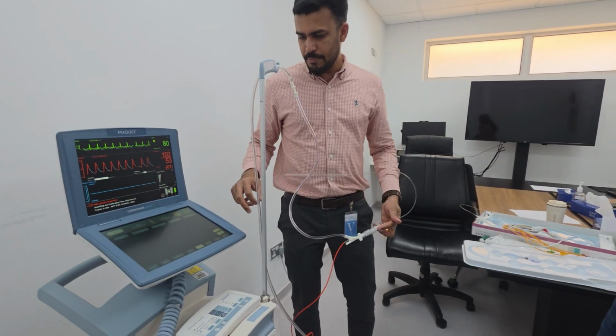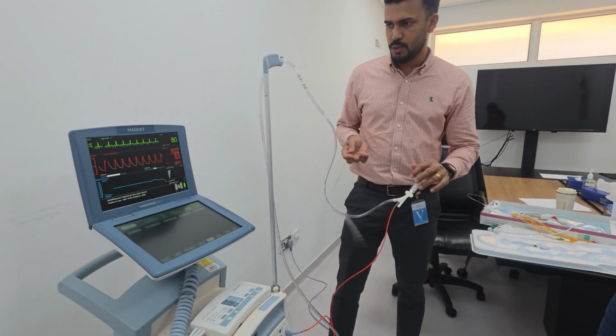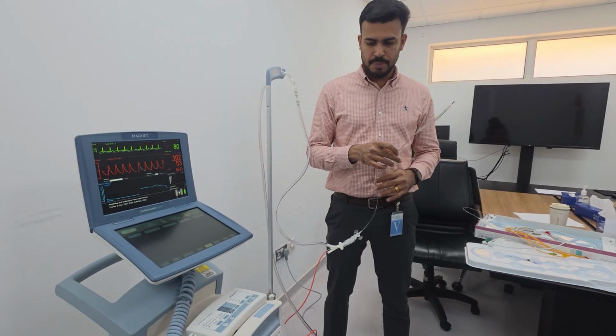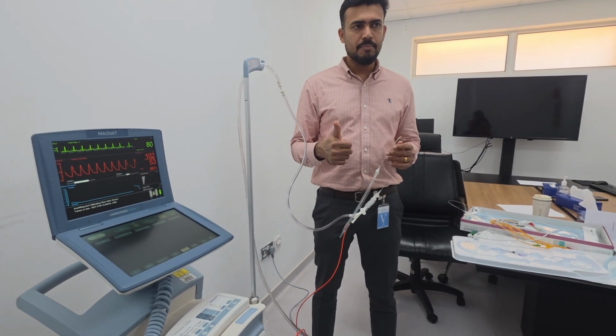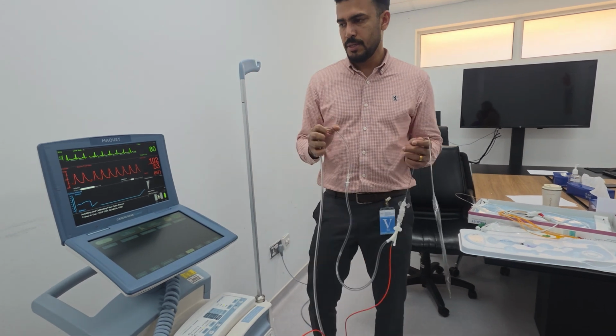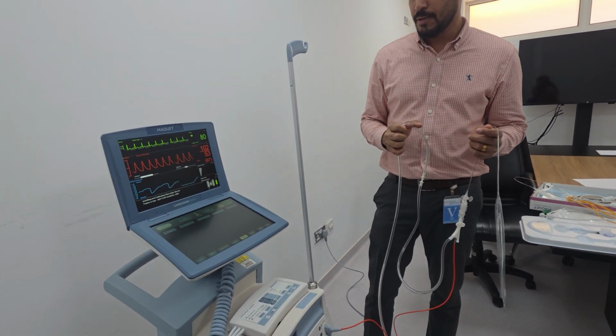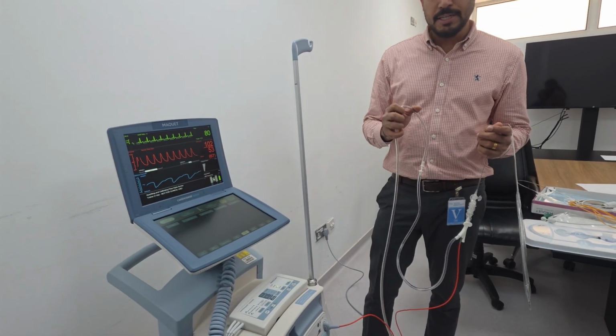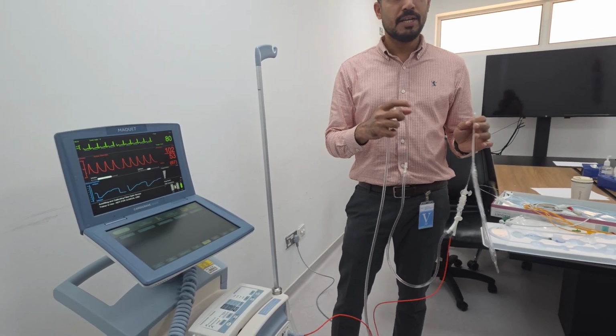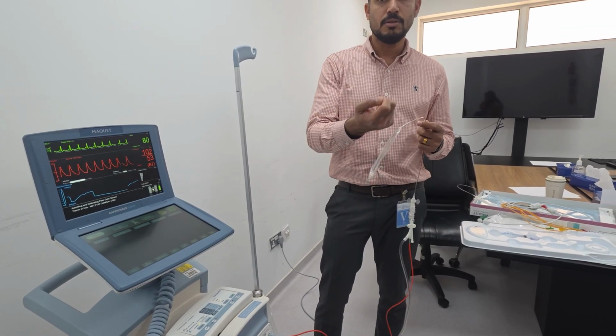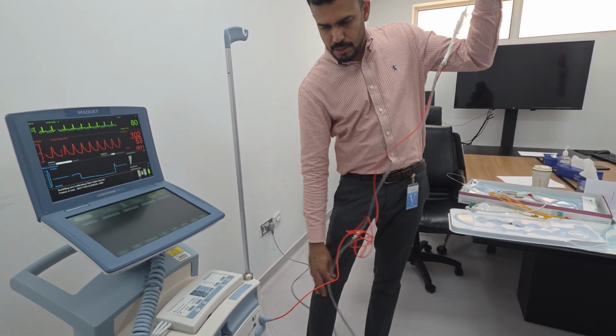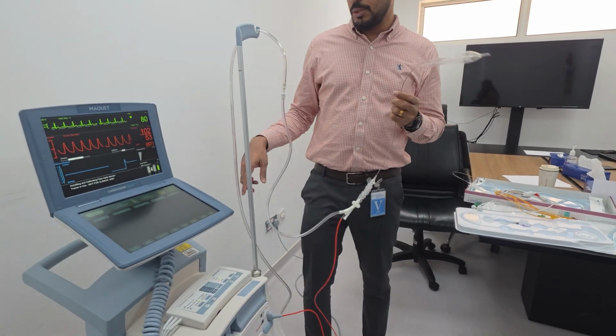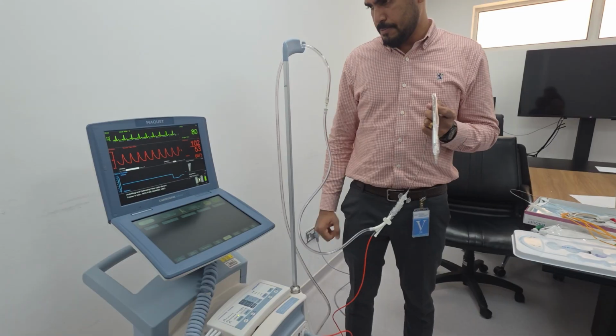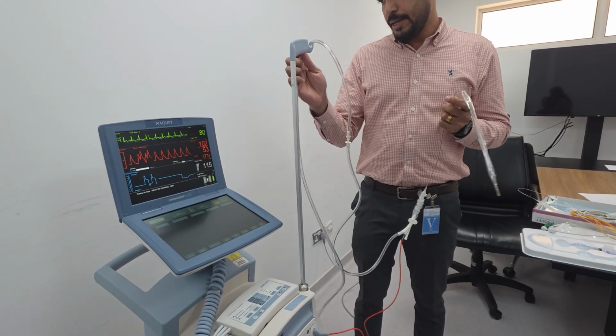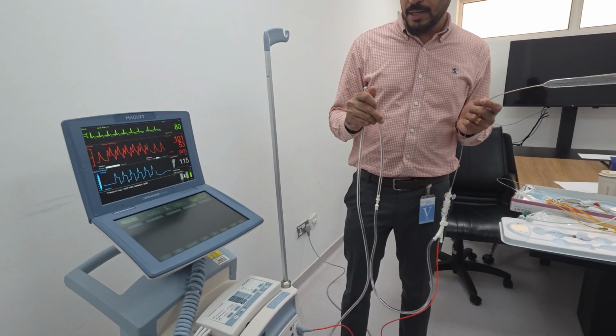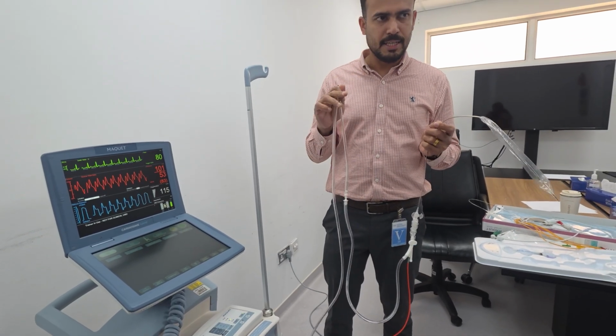I will show you one more time. This is the autofill procedure, autofilling and calibrating fiber. In case you are ignoring this alarm, there is a method I'll show you. Let it finish. So always give more attention to catheter alarms, because if you ignore that alarm and there is an actual leakage, blood could come inside the machine. To avoid this, do a manual autofill now. I'll show you. It starts pumping. I will create a kink again. We will consider this as a leakage also, for any catheter alarms.